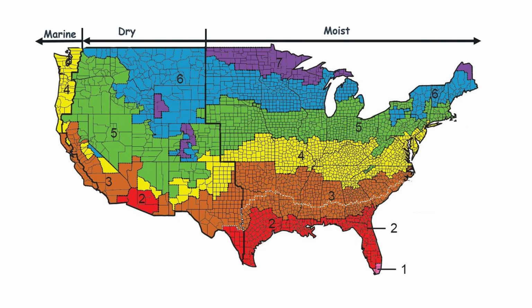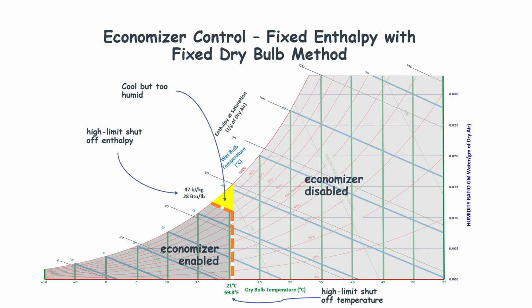This control method is very useful for projects in regions with high humidity. In these regions, the economizer may add unwanted humidity to the indoor spaces by bringing in humid outside air, even when that outside air's dry bulb temperature is below the high limit shutoff value. But this issue can be eliminated with this control method, which considers enthalpy too. On the chart below, the highlighted area shows the outside condition that is cool but too humid to be used by the economizer.